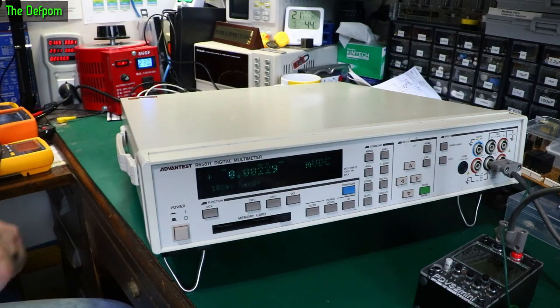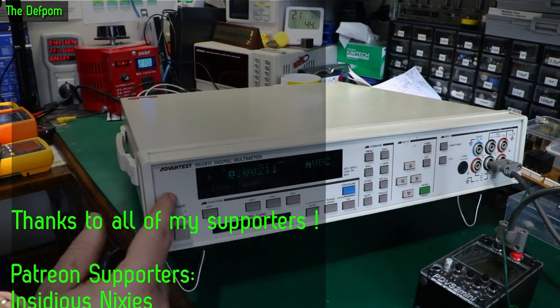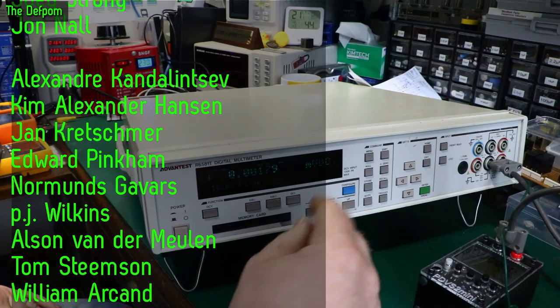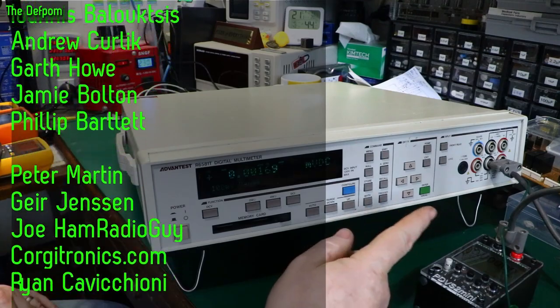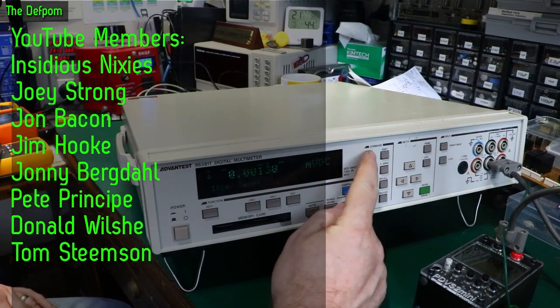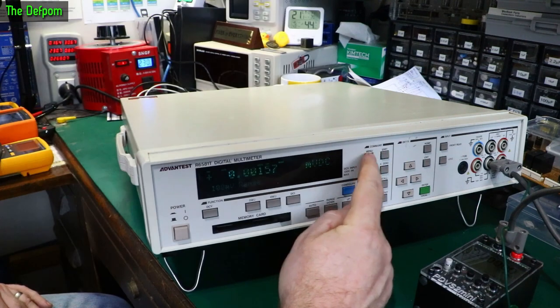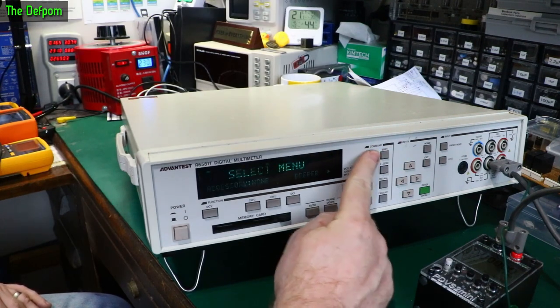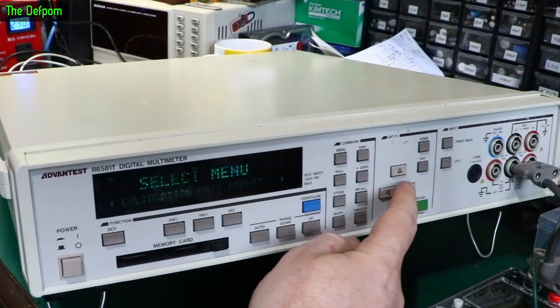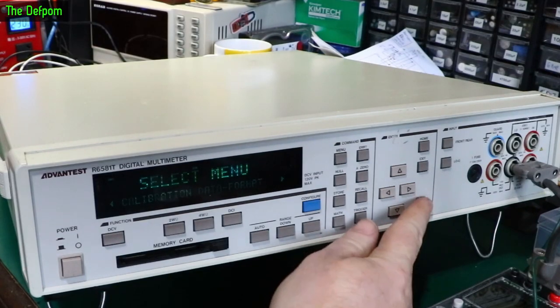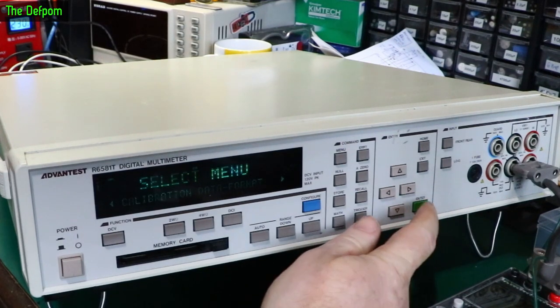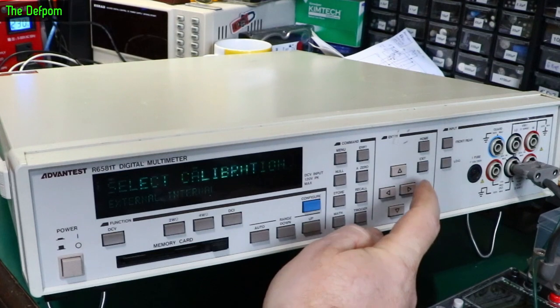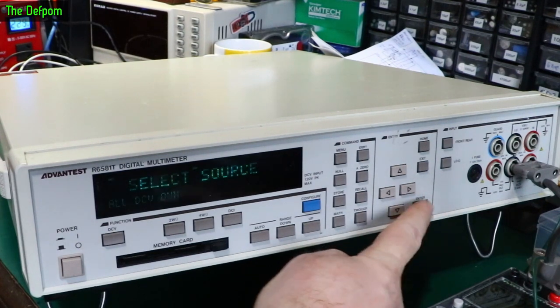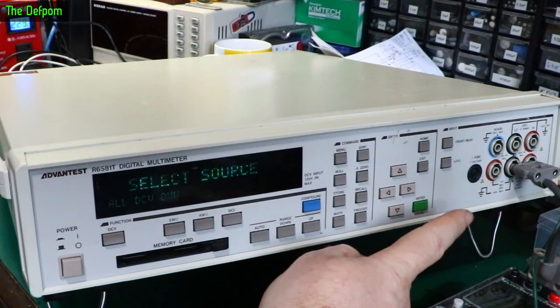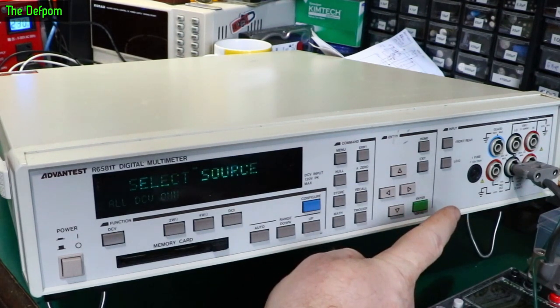But I think it's probably just a bad battery. What I'm going to try doing is an internal calibration on this. You can do an auto internal self calibration, which may solve the problem if it's because of the battery. A common problem on these apparently is the battery can be a problem. So when a battery goes flat, that can be one of the symptoms it has. If I just get the menu to come up, there we go. Calibration. Enter. Come on. Internal calibration. Yeah, it's the ALL. Come on.